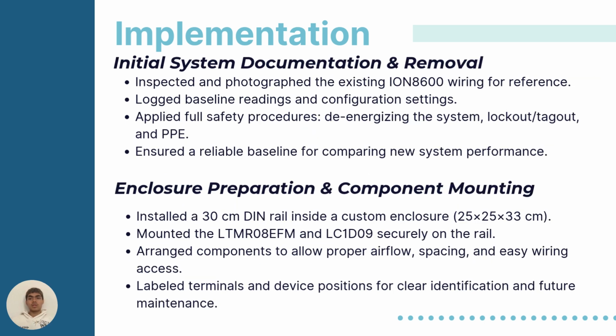Yep, so initial system documentation and removal. Inspected and photographed the existing power analyzer as I've mentioned before, and logged baseline readings and configuration settings, and applied full safety procedures, like we turned off the whole system before taking the power analyzer out of its original place. So enclosure preparation and component mounting. So this just talks about the size of the enclosure, which is 33 cm long, 25 centimeter wide, and 25 centimeter tall. And there is this DIN rail which holds both the relay and the contactor together to avoid the parts moving inside the enclosure. So it is 30 cm long as well.